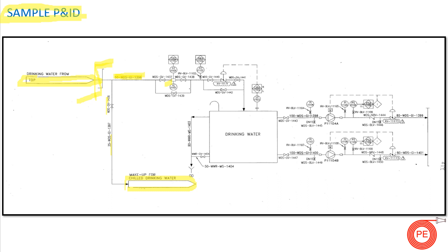Every piece of equipment has been provided a tag. The tagging or nomenclature of pipelines, valves, and instrumentation depends on the company — every organization has its own tagging philosophy. The key point is that when reading a P&ID, the first thing you should look for is the tags, since everything shown in a P&ID has its own tag or nomenclature. You can see the pumps are shown with their tagging, and the general instruments that are part of the pumping system — on the suction side there is a gate valve, then a pressure indicator or pressure gauge, and on the discharge side there is a pressure switch or pressure transmitter, followed by an NRV and an on/off valve.